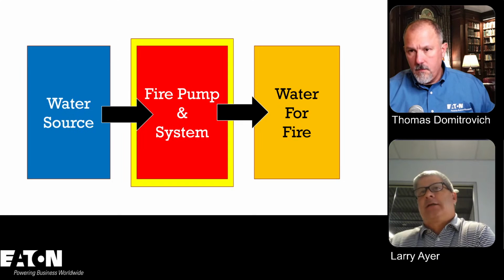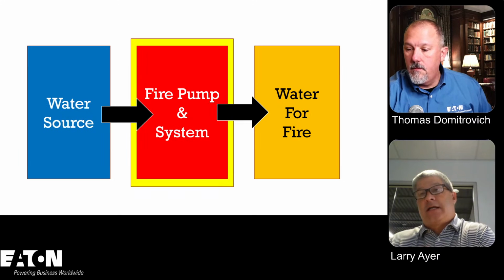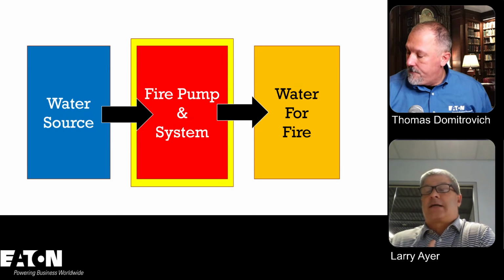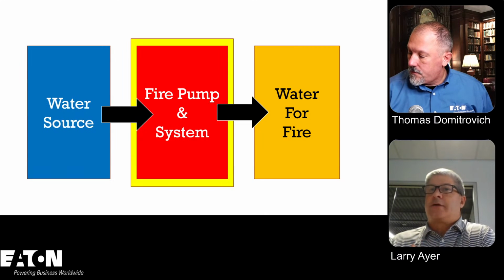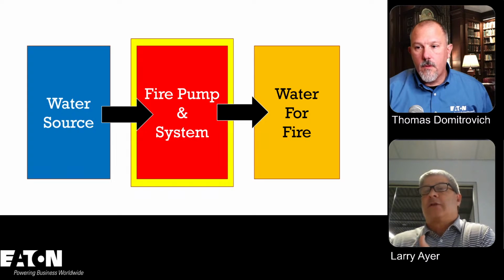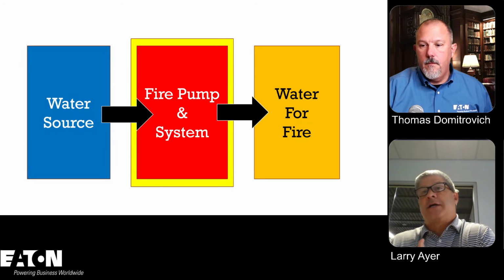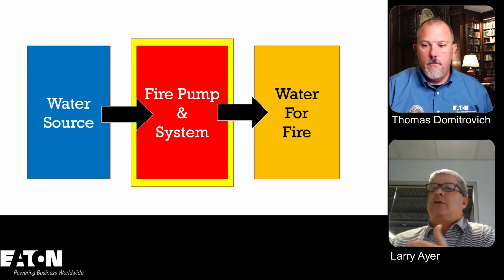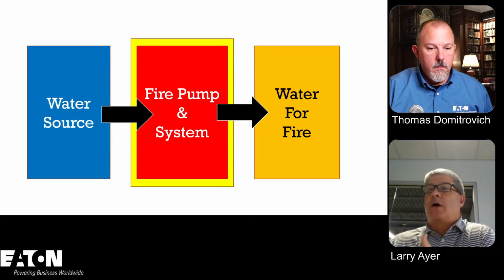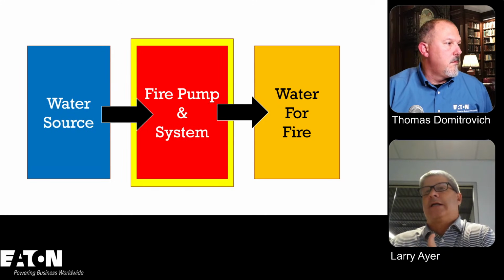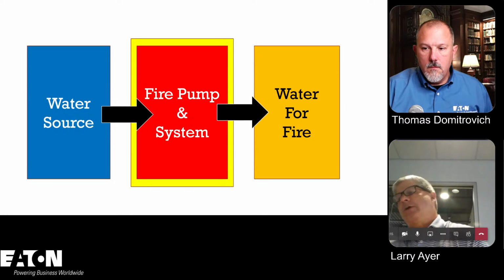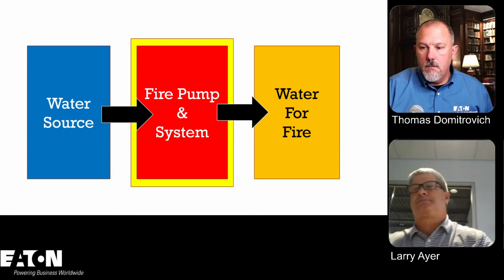And I think typically, and it depends. Typically, I see that sometimes you need 7 psi to get to that last sprinkler. So what you do is you do flow tests out there, and you look at the static pressure where there is no water flowing, and then you simulate water flowing through the fire hydrant, and you draw a couple lines together, and then you look to make sure, okay, what happens if I have sprinklers go off? What happens if I need 250 gallons per minute from a fire hose and from a sprinkler going off? And so then you estimate what the pressure would be, and if the pressure is too low, you need to supplement that with some type of fire pump or things of that nature.